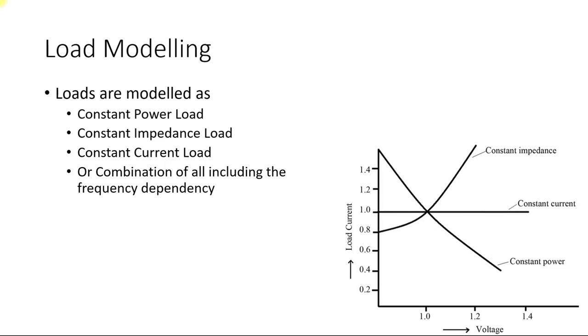An example of a constant current load is a battery, because irrespective of the voltage or power provided to the battery, the charging current should remain the same. When modeling a load, you need to know what kind of load you have. If you have a lighting load, model it as constant impedance. If you have a motor load, model it as constant power. If you have a battery or electronics circuitry that draws constant current, model it as constant current. Or it can be a combination of all three — in such cases, you provide a lump load which is a combination of all of these.